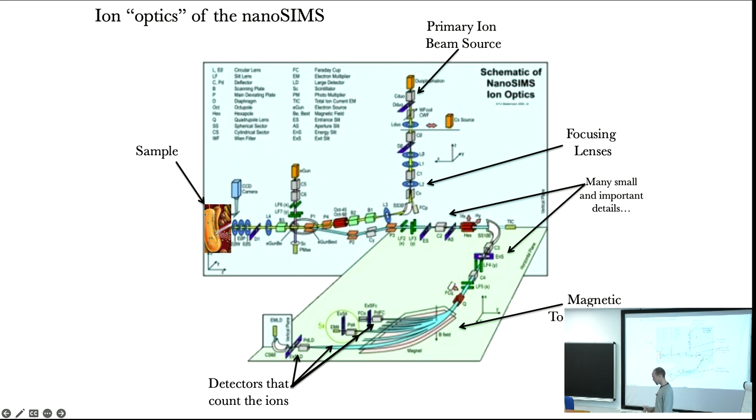They started out making these with five, now they make them with seven, you could go to 10 or 15. But you do run into problems with the current and how much space you have available here. For example, the instrument at Caltech, the data that I'm going to show in a slide or two, the operator of the SIMS, he's wonderful, and he's the type of person that we could say, we want to measure deuterium and protons and 13C at the same time. You can't do that with the commercially purchased instrument. You don't have a big enough radius, you don't have a big enough width to catch HD and way over here 12, 13, and then the 15N species and 14N species.